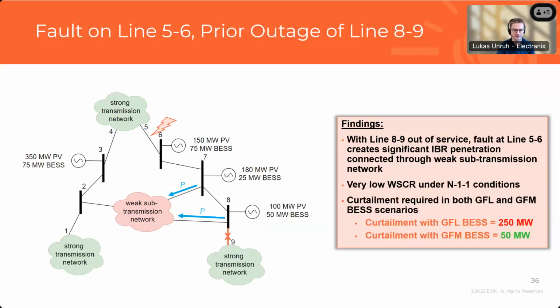And then the last scenario I'll point out is an N-1 fault, where we basically removed both connections from that corridor on the right and left, with all of the IBR generation there operating into that weak sub-transmission network. And this scenario was unstable for grid following and for grid forming when all the devices were dispatched to PMAX. So we tried to see what kind of difference in curtailment would be needed for grid following versus grid forming. And yeah, it was quite a big difference.